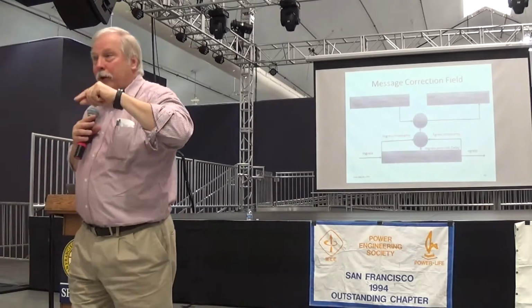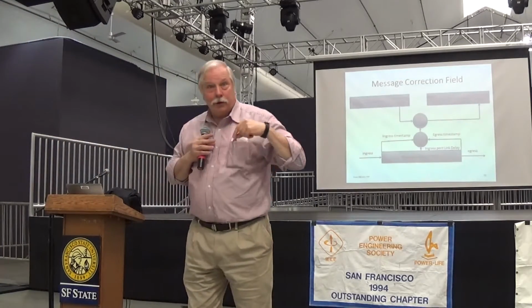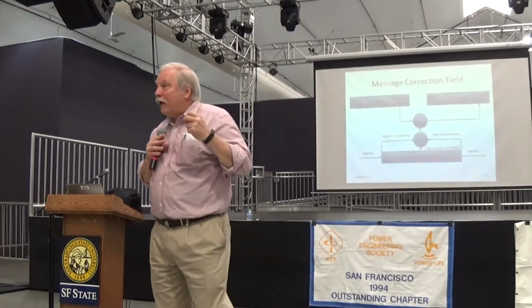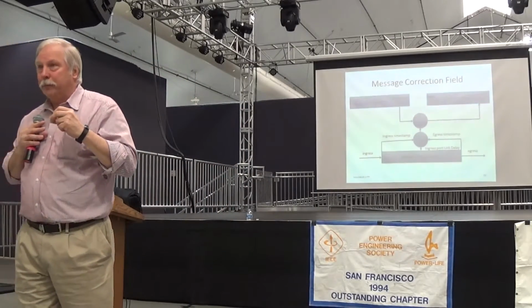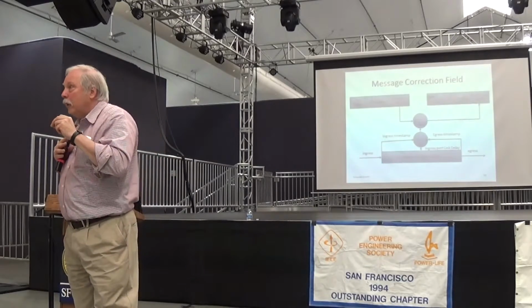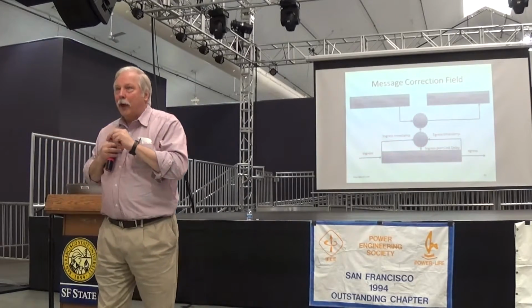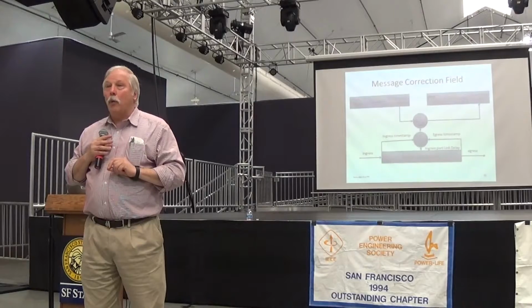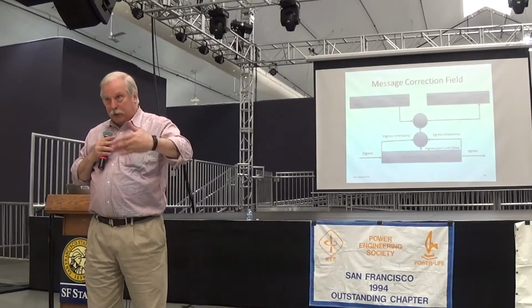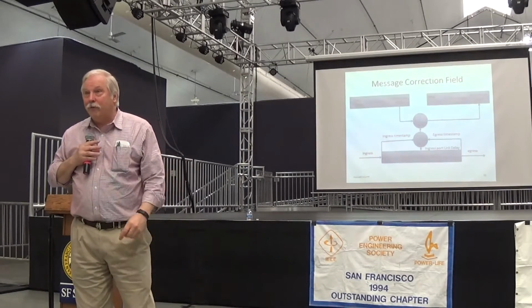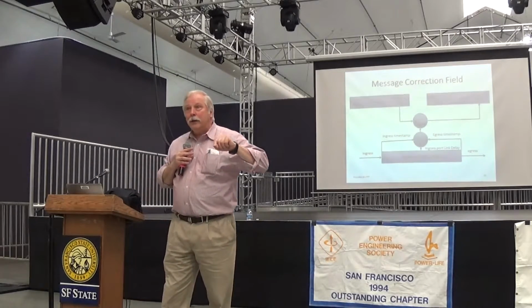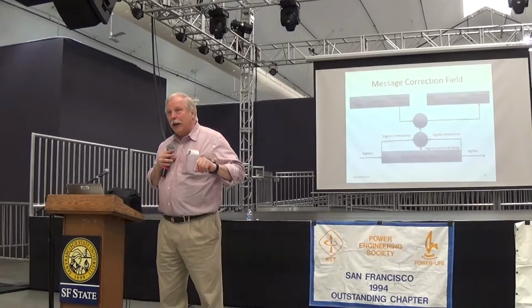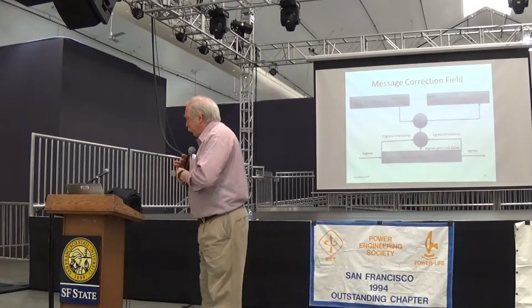When the message comes in, there is what's termed residence time inside the Ethernet switch. There are special Ethernet switches that are 1588 aware. So you do need to use a 1588 aware Ethernet switch if you want to get precision time.